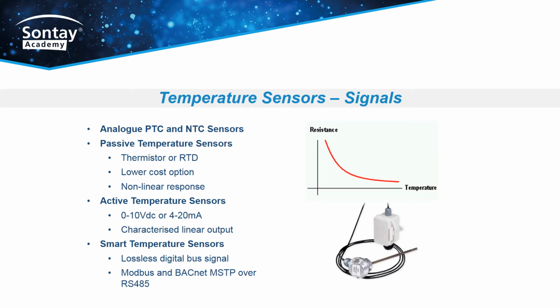and resistance. Each type of resistance temperature sensor has its own set of benefits, and it is important to choose the correct sensor for your application. Active signals are generally either 0 to 10 volts DC or 4 to 20 mA. In the case of a temperature sensor, this is generally derived using a platinum RTD inside the sensor unit, which is then fully linearized as an active output. Most other sensors, for example relative humidity or pressure sensors, have active 0 to 10 volt DC or 4 to 20 mA signals, and passive signals are uncommon outside of temperature sensing. Smart sensors provide lossless digital signals to communicate their values back to the BMS. These are covered separately near the end of this presentation.